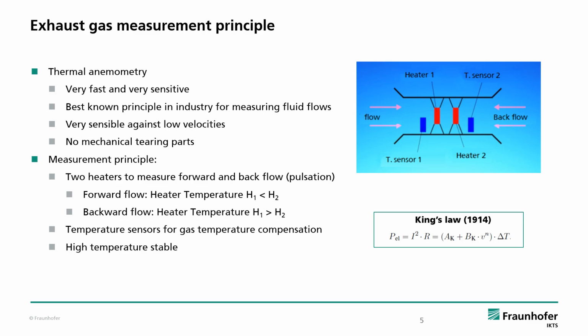As you can see, there are two heaters in a row and two temperature sensors in a row. With two heaters in a row, you can measure forward and backward flow very fast, which is needed to detect pulsations. So for forward flow, heater 1 is cooled more than heater 2, and the other way around for the backward flow. The temperature sensors measure the gas temperature, and with this information the heater temperature is set. It is constant 100 Kelvin above the gas temperature.